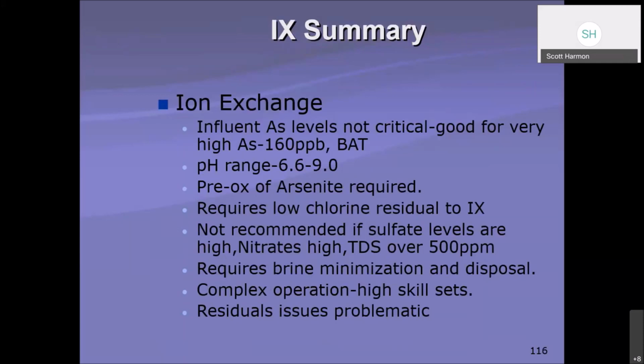Not recommended if sulfate levels are high, nitrates high, or total dissolved solids over 500 parts per million, because it'd be way too much of a load on your brine. Other contaminants would exhaust your brine. The arsenic removal may not be as complete. Requires brine minimization and disposal. Again, disposal with all these different concepts is going to be an issue.